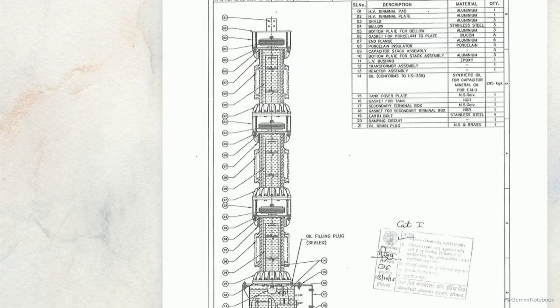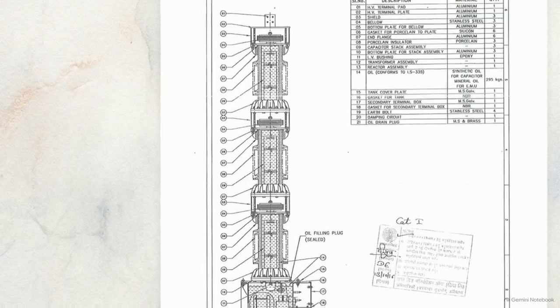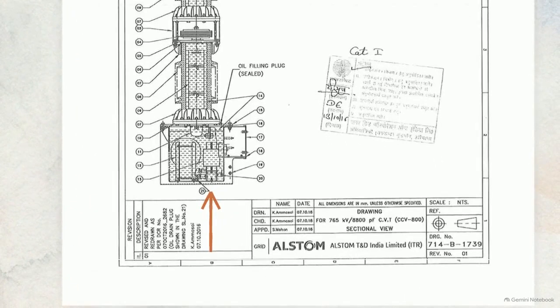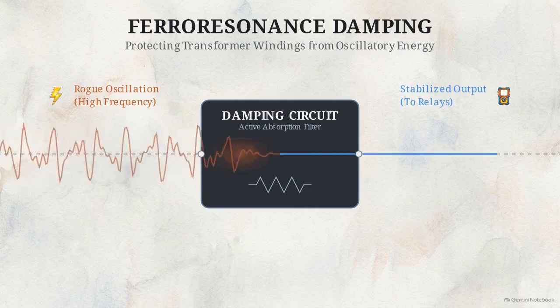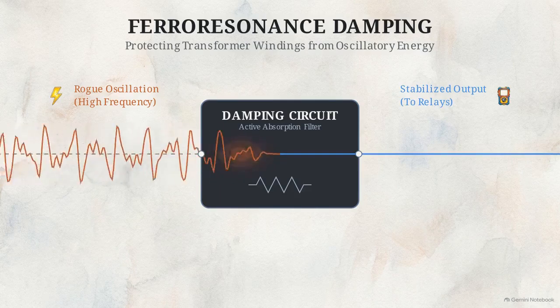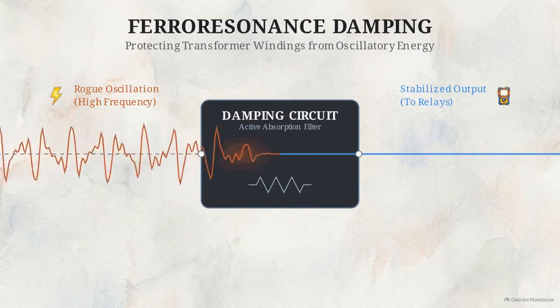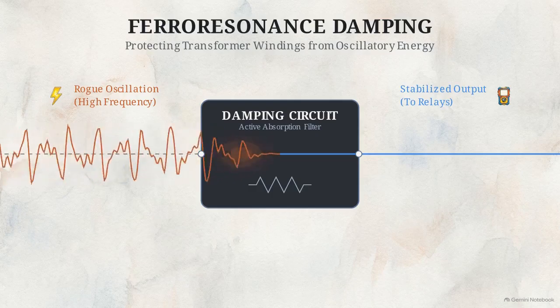To protect the internal components from the thermal and electrical stress of these oscillations, engineers include a final component in the bottom tank, a damping circuit. Wired across the secondary terminals, this circuit is designed to instantly absorb and dissipate the rogue oscillatory energy before it can damage the transformer windings.